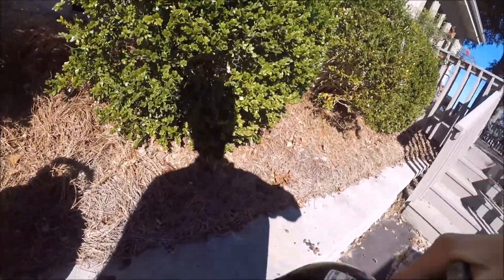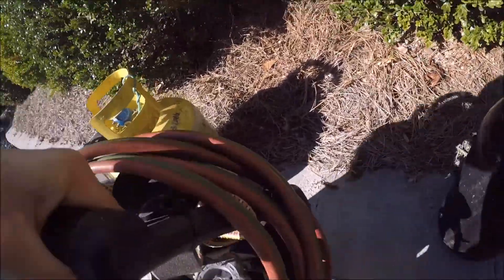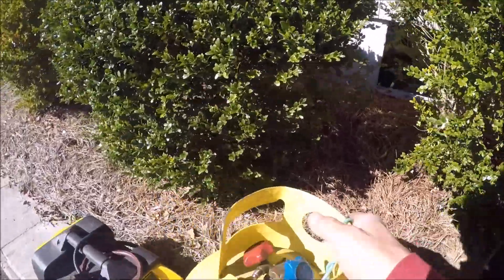It's Friday morning. Today we got to replace an expansion valve in a water furnace. It keeps locking out on the water flow in heat mode. We are at the job and we got to change this expansion valve in this geothermal water furnace.